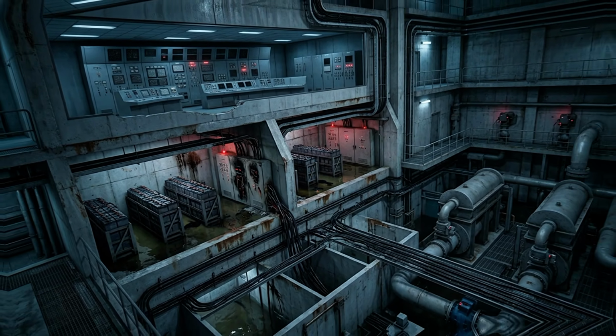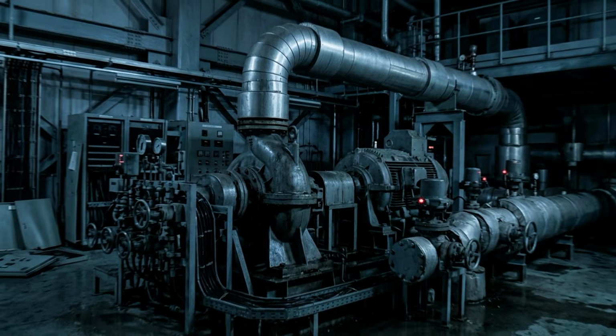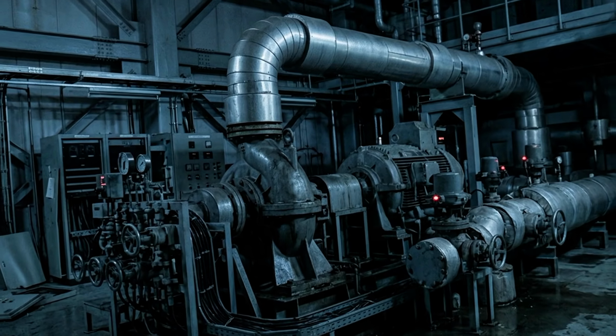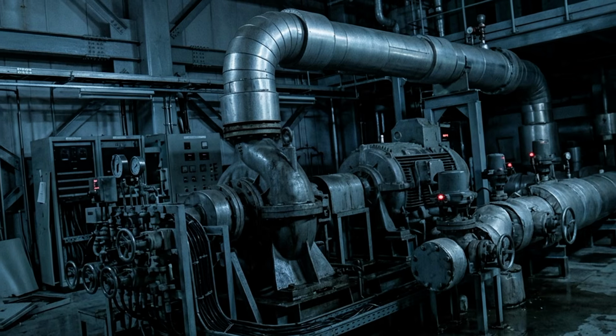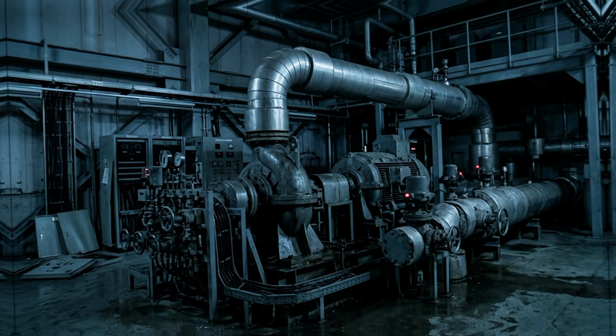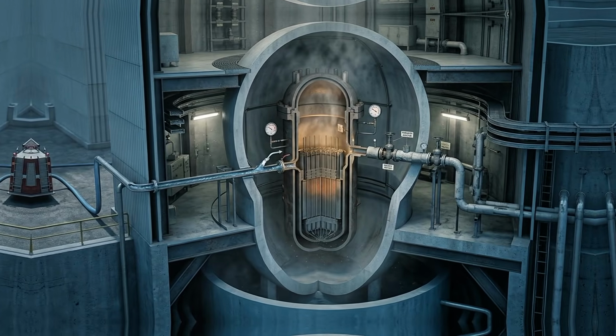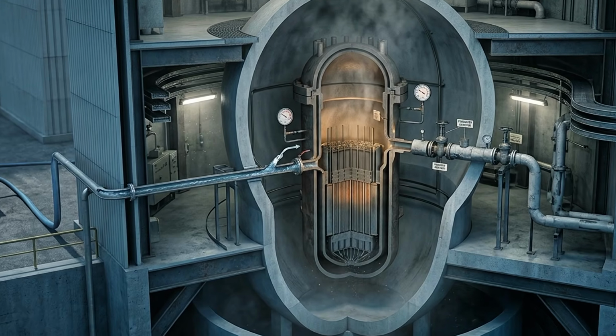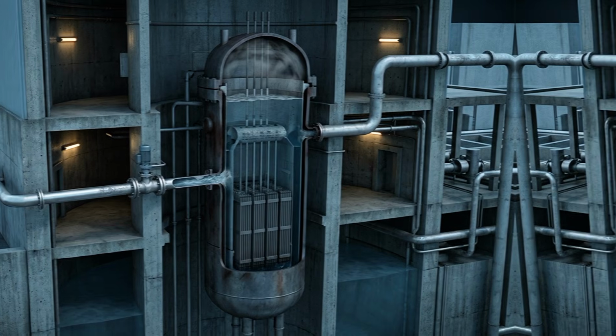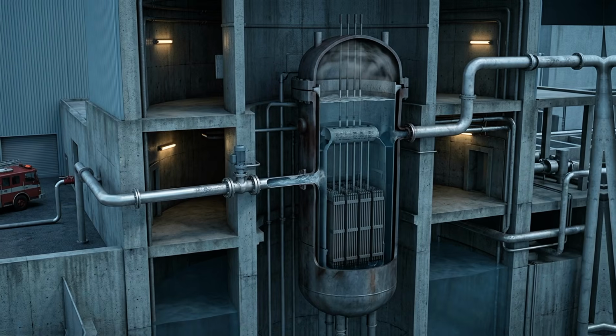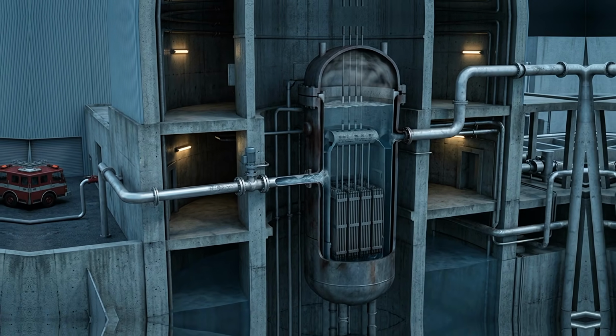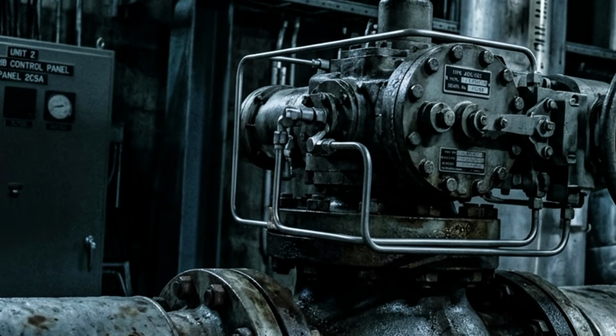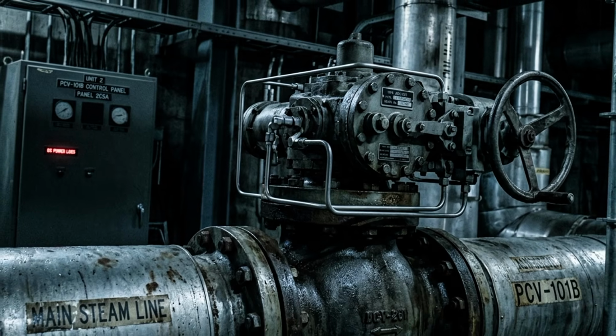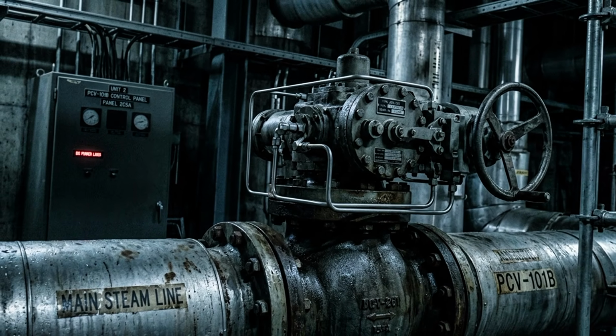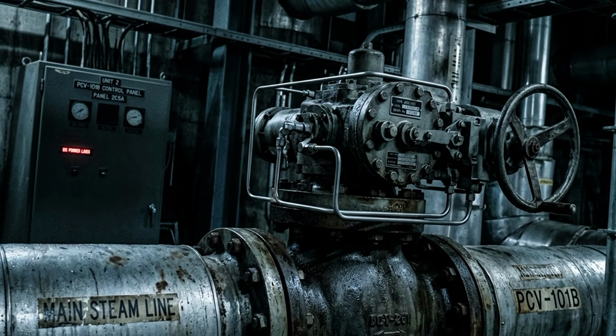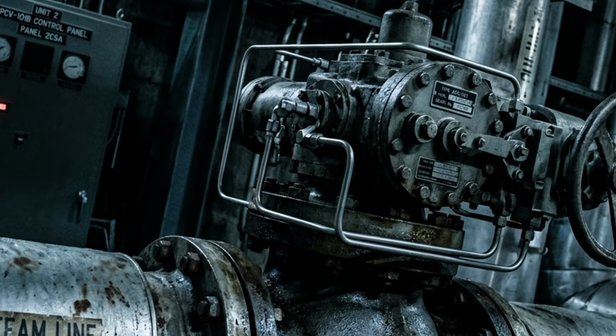Other emergency systems were also affected. At Unit 1, high-pressure coolant injection could not be maintained after the loss of DC power needed for its operation. As pressure and temperature changed, alternative water injection became increasingly difficult. Low-pressure injection could not simply force water into a reactor vessel that remained at high pressure. The reactor had to be depressurized sufficiently first. But the valves and supporting controls required for pressure management were themselves affected by the loss of power and instrumentation.